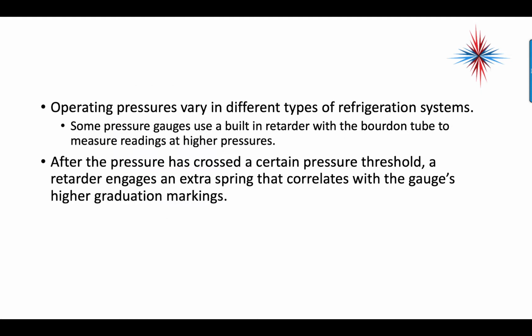Operating pressures vary with different types of refrigeration systems. Some pressure gauges use a built-in, it's called a retarder, with the Bourdon tube to measure readings at higher pressures. After the pressure has crossed a certain pressure threshold, a retarder engages an extra spring that correlates with the gauge's high graduated markings. In other words, there's a point in here where it's actually going to shift values to a much higher pressure.